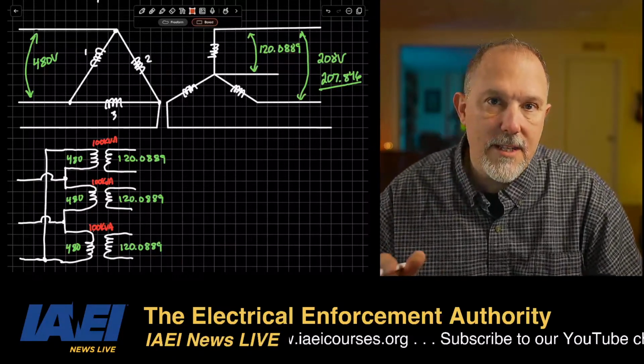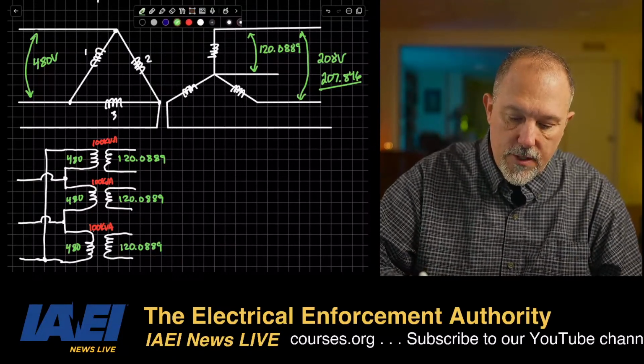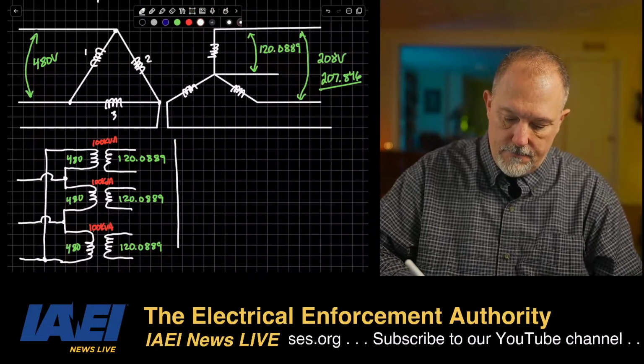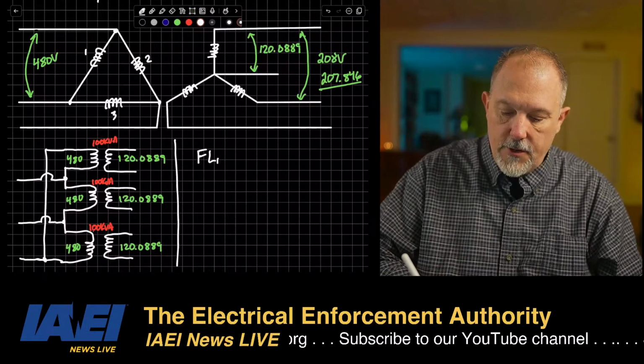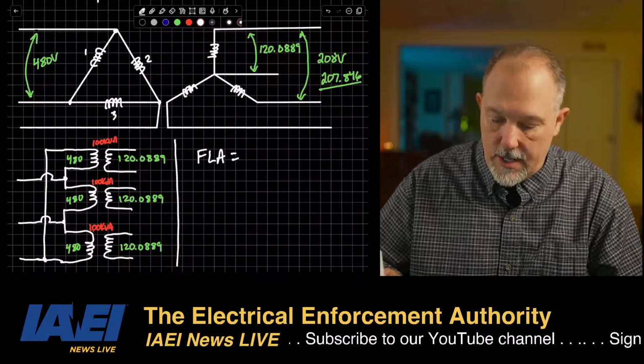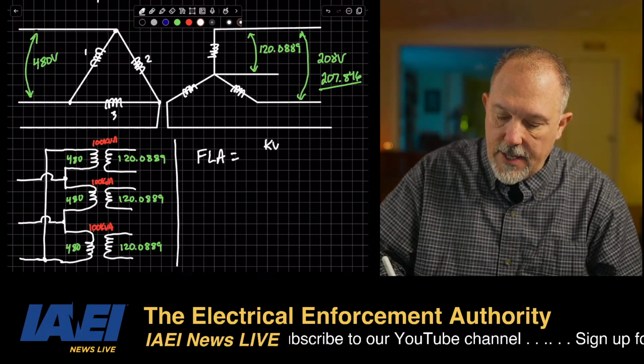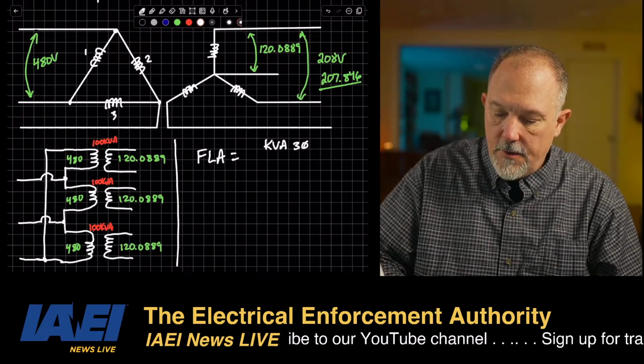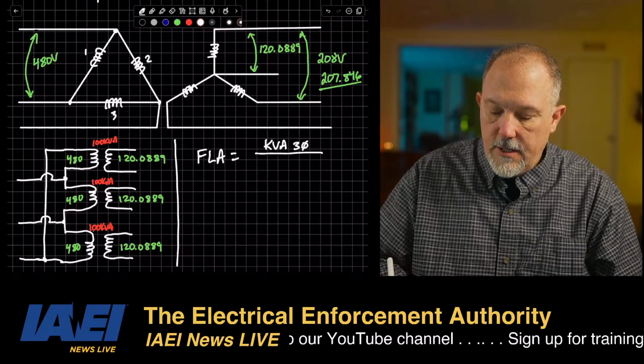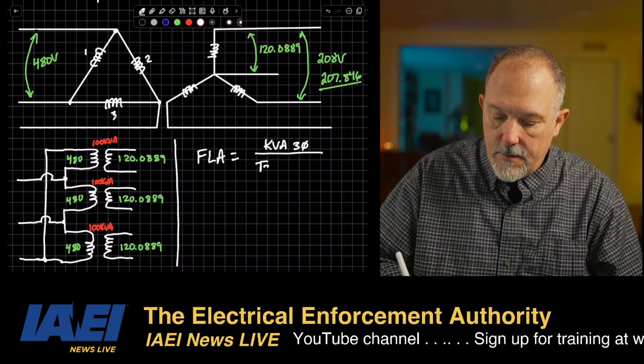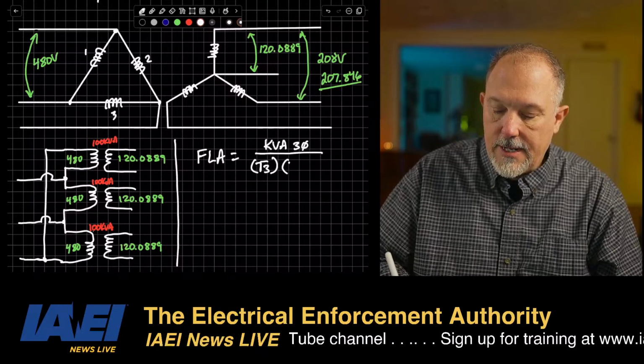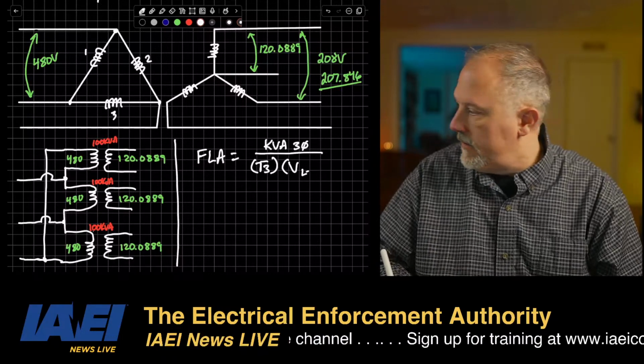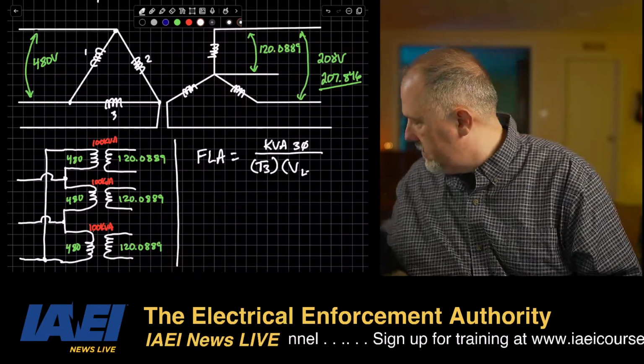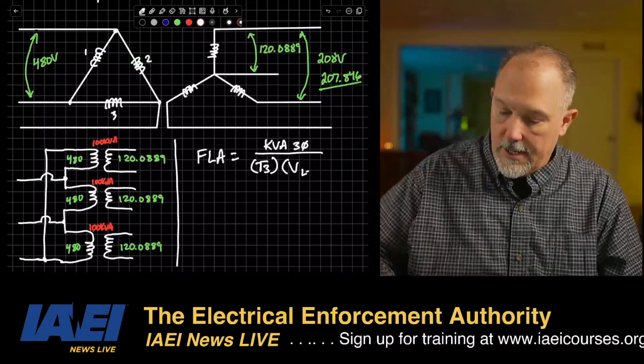Now, what is the calculation we use for transformer full load amps? Full load amps is equal to what? kVA three-phase, divided by the square root of 3 times voltage line to line.